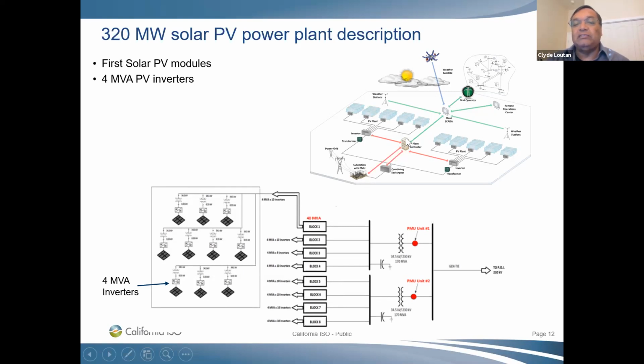But at the top here, you have this plant controller that controls those inverters. So in other words, if the ISO or any balancing authority sends instructions to a PV plant, even though the PV plant has individual inverters, the plant controller, which today is needed on the grid, coordinates all the responses from the individual inverters to make that plant operate like a large synchronous resource. The plant controller is, as I said, a smart controller. It would move those inverters to react to a dispatch signal from, let's say, the California ISO. So we tell our solar plants to move up or to move down.